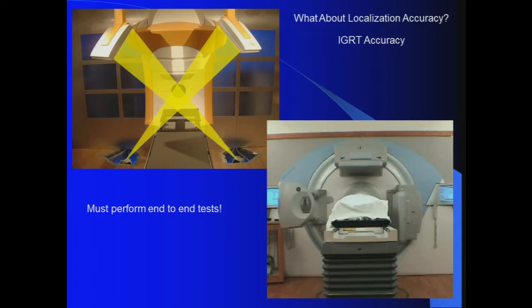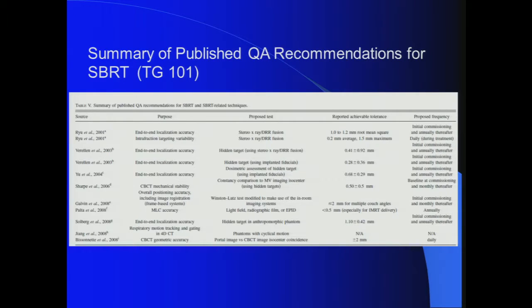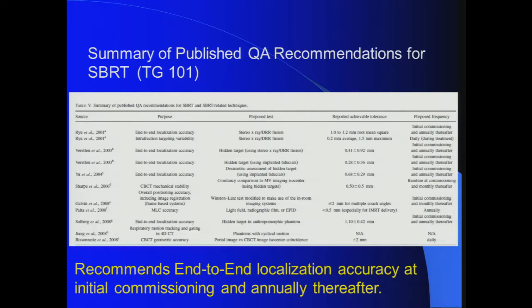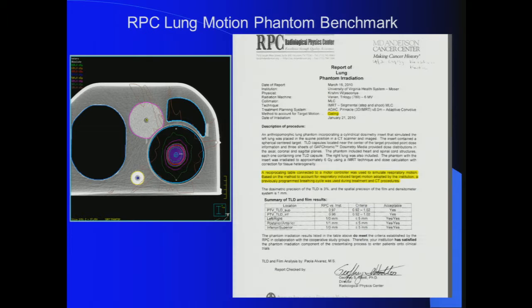We're not just looking at those issues, we've got a variety of others. What about localization accuracy, IGRT accuracy? You must perform end-to-end tests at least once a year, certainly upon commissioning, and at least annually. TG101 recommends end-to-end localization accuracy testing at initial commissioning and annually thereafter, to make sure you haven't lost your way during the course of the year.